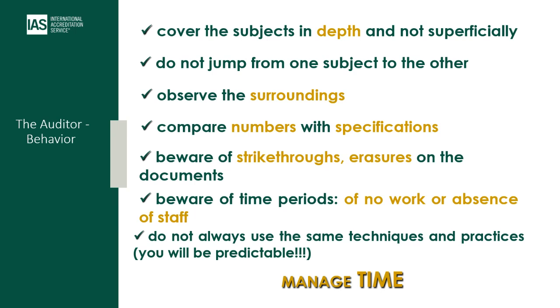All right. Cover the subjects in depth, observe the surroundings, compare numbers, beware of strike-throughs and erasures, beware of the time period. If a lab is working on a two-shift basis and you're doing the audit on a late shift, you may not be seeing all of the processes that are done in the early shift. Okay, so manage time. Next slide, please.